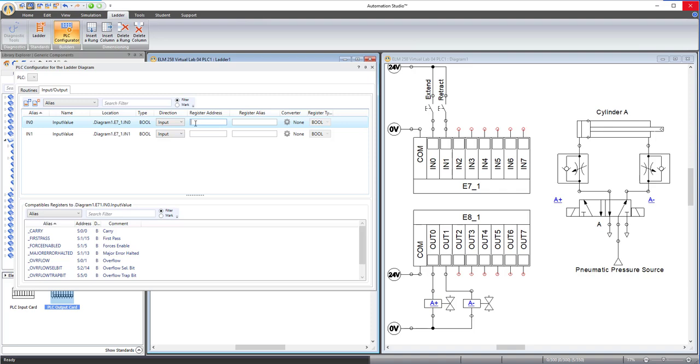So the syntax in Automation Studio is I for input, which is typical, then a colon. Now it's 0.0, so that's slot 0, sub-element 0. I know in a lot of addressing the sub-element is not used, and you have a more simplified address, which would be like I:0/0, 1, or whatever the bit number is. So in0 has the address I colon 0.0/0. And we're going to give it an alias, which is basically the name of the input.